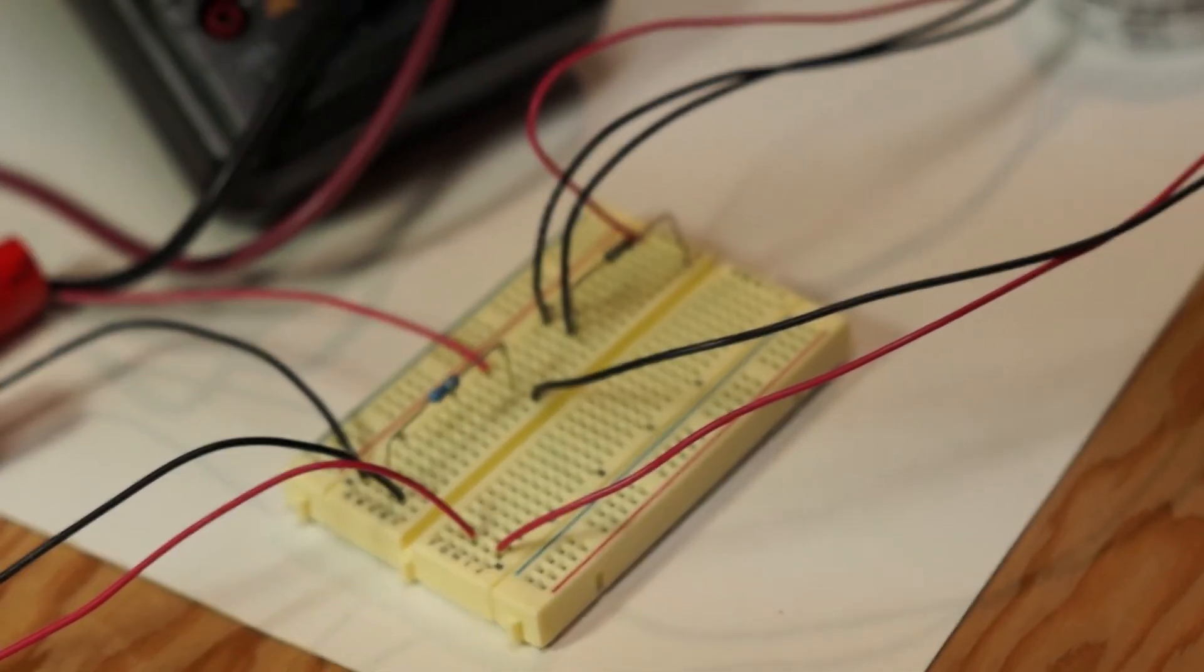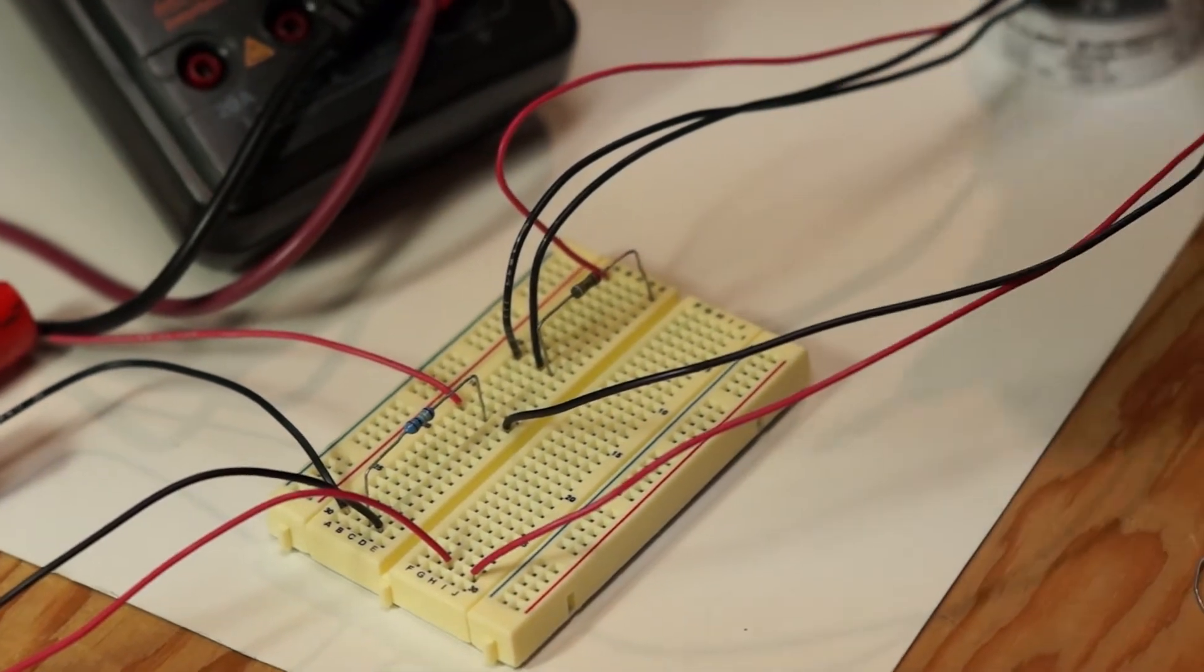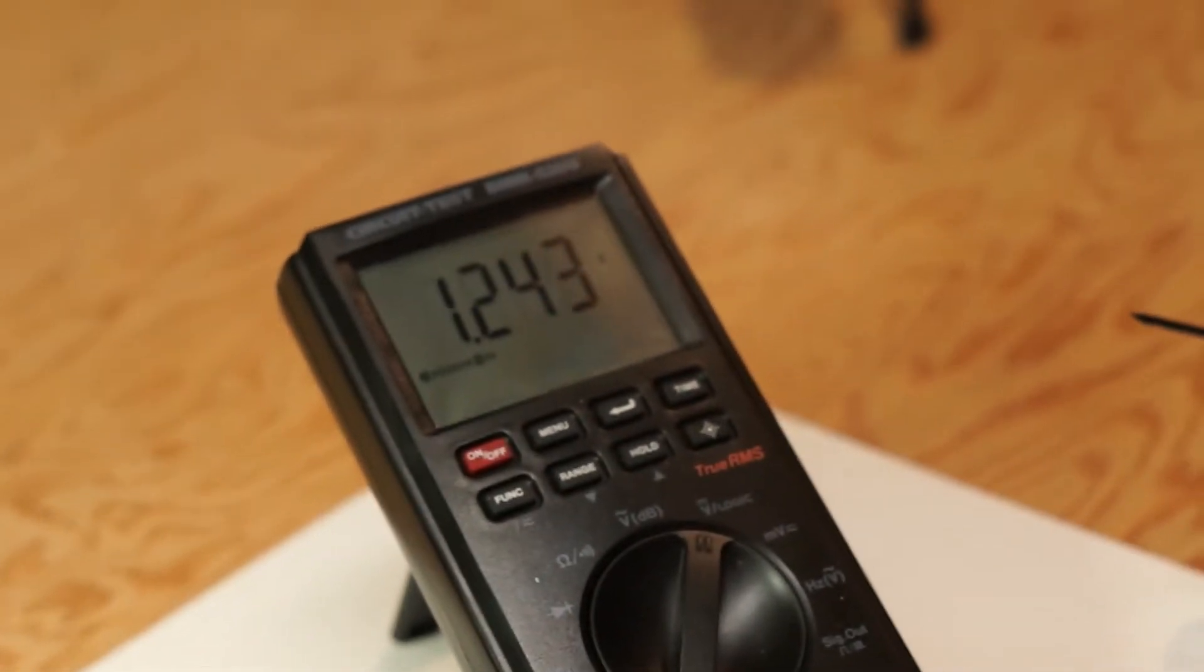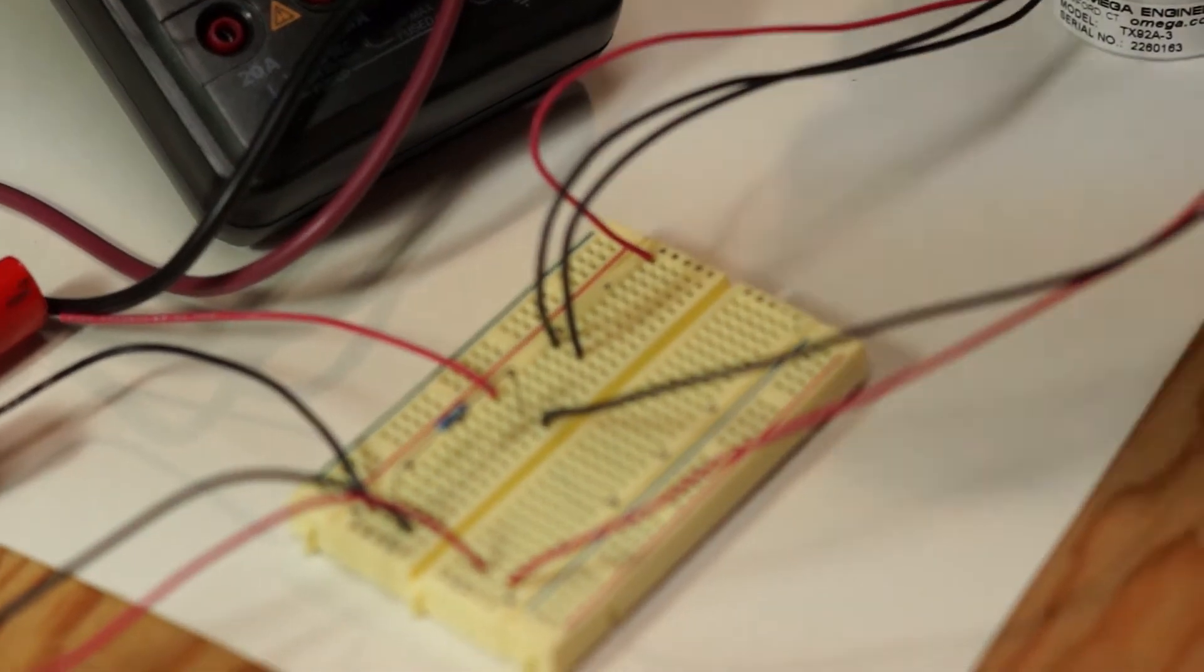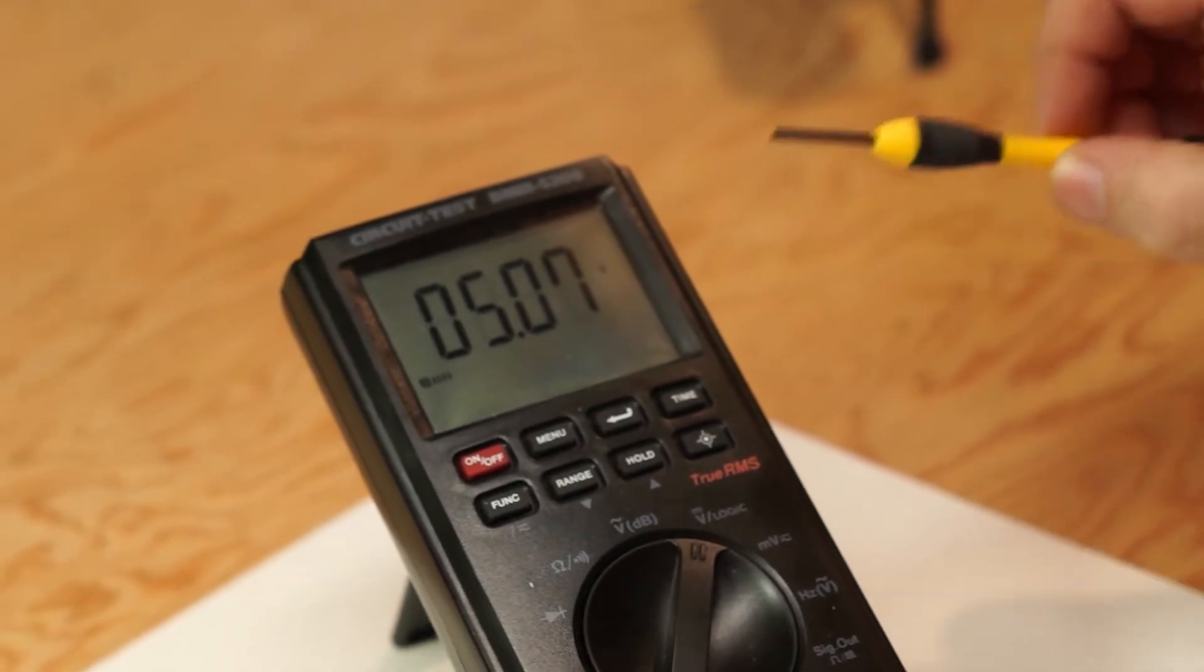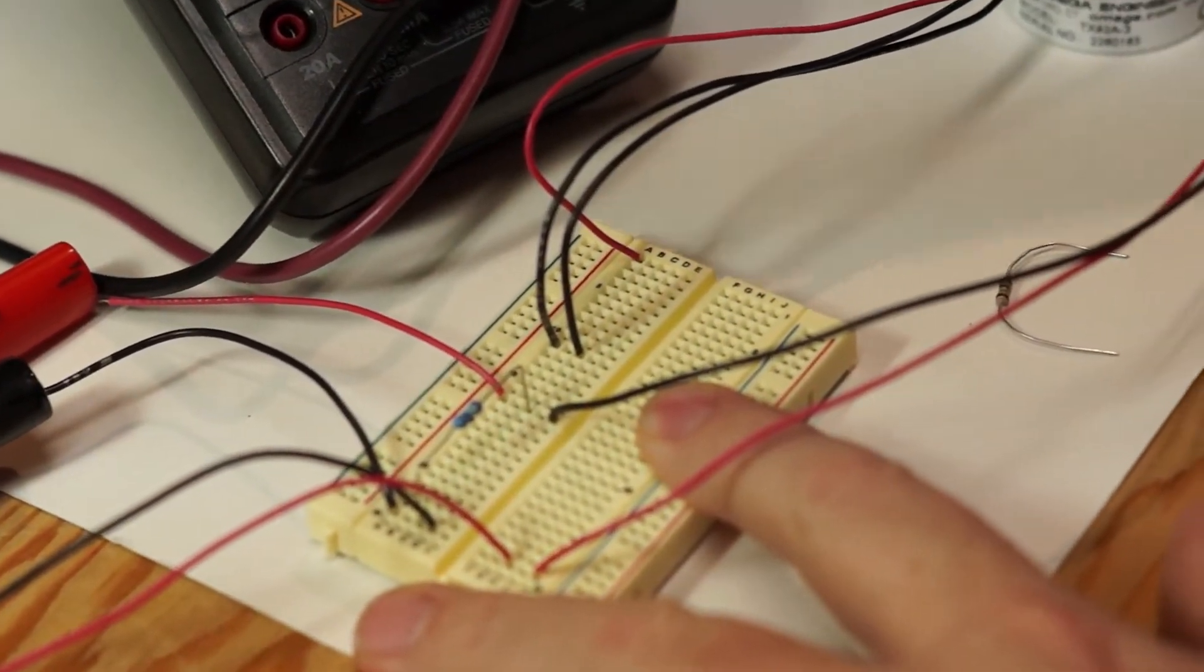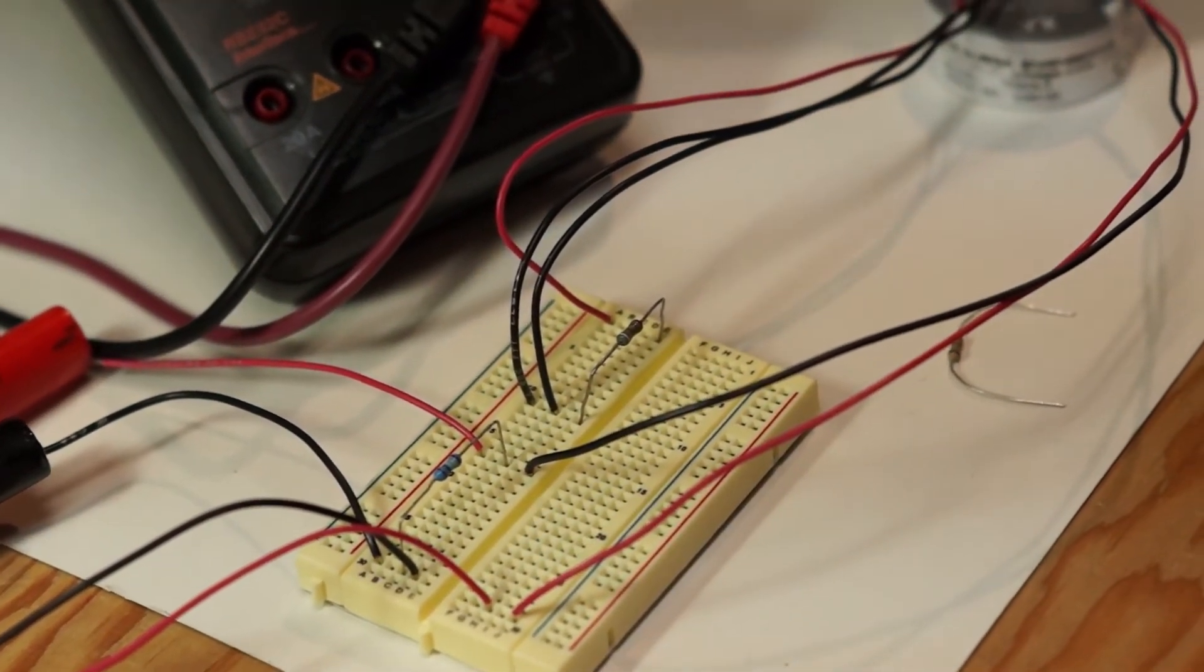All right now I'll take you through the steps of actually calibrating the device and I know it's out of calibration right now because I'm simulating the low end with a 93 ohm resistor and it's not reading one volt as you can see on the meter which it should be at its lowest temperature of zero degrees and I'm going to be simulating the highest temperature with a 150 ohm resistor. I'm going to place it in here to simulate an RTD at 300 degrees which should be giving me five volts and I'm getting close to that but I need to adjust it a little bit more. Now normally you want to start with the zero input so back to the other resistor and I will be going back and forth quite a few times until it's calibrated.